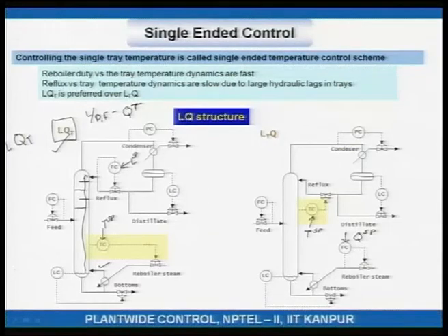On the other hand, if I increase the reflux, by the time the reflux or the liquid flow rate changes on a tray that is say 10, 15 or 20 trays below, it would take, you know, 5-10 minutes, because each tray would have a residence time of the order of 30 seconds to a minute, right. So, 30 trays is a residence time of the order of about what, 20 to 30 minutes, all right.